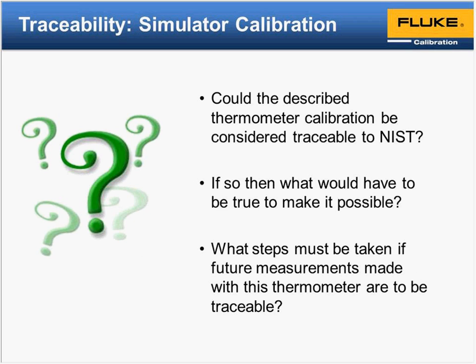The routines we're going to run through are all hypothetical, building upon each other. The other thing to consider is running into the linear slope issue where, say, you adjust 0 right at 0, and then we go to 100 and trim that one right in at 100, and then come back to 0 and we're out. Again, remember in our example, we were trying to hold to plus or minus 0.2. So somewhere along that slope there is a little bit of an issue. Even with the adjustments at 0 and 100, sometimes it's good to check some midpoints, say 50, or even 25, 50, and 75, to see where you're drifting in that slope.